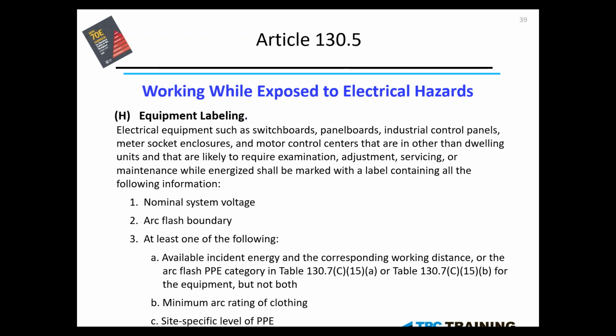What equipment needs to be labeled? What different types of equipment need to be labeled? We need to take a look at, and I like the way they word this in the code book, it says electrical equipment such as, and it doesn't say every piece of equipment that follows. It's just such as. So they're going to leave that up to the authority having jurisdiction to identify which equipment needs to be labeled.